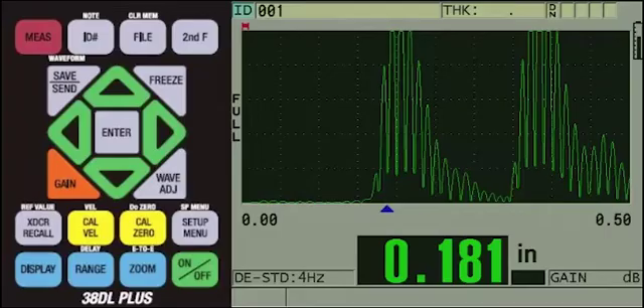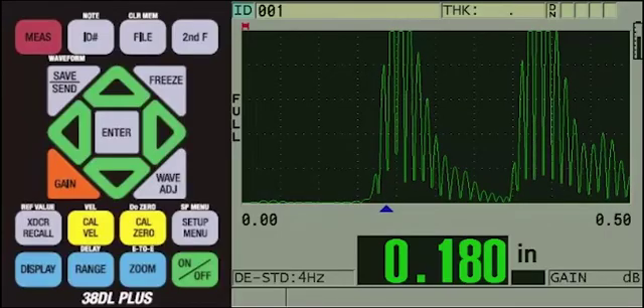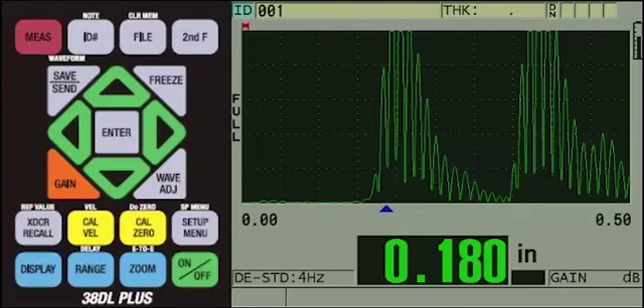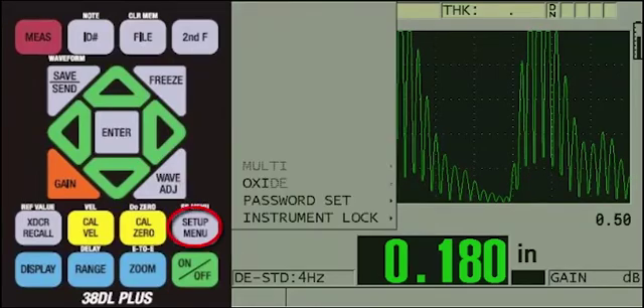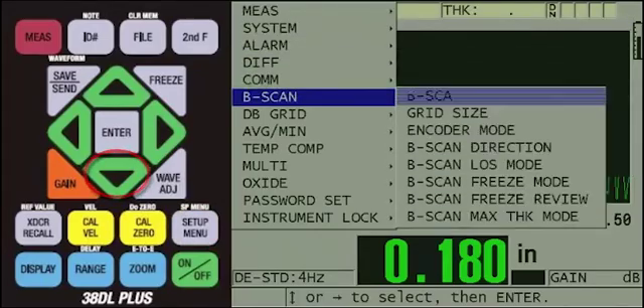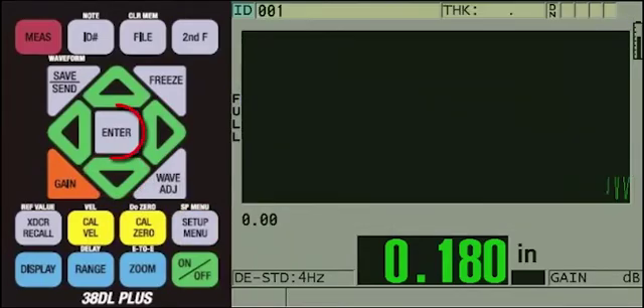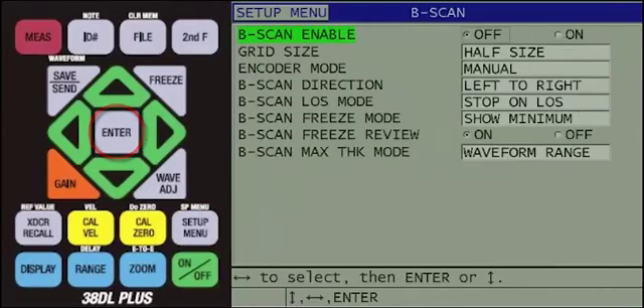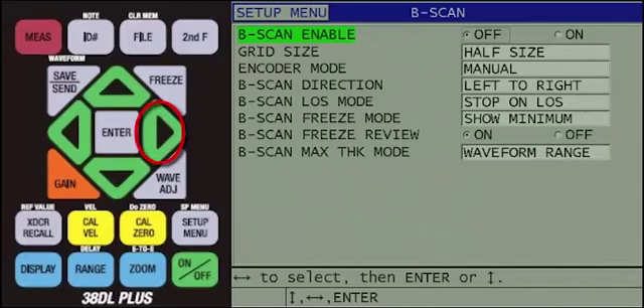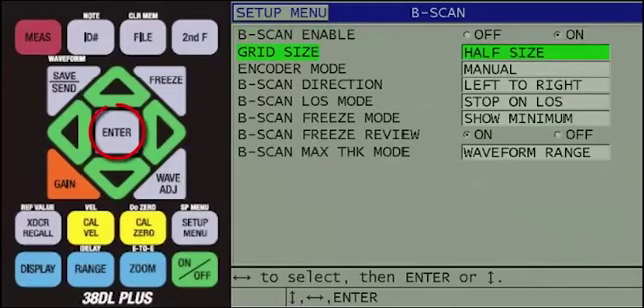At this point, we can enable B-Scan on the instrument. To do this, press the Setup menu key, then press the down arrow to highlight B-Scan, and then press the Enter key. Use the right arrow to enable B-Scan to on, then press the Enter key.